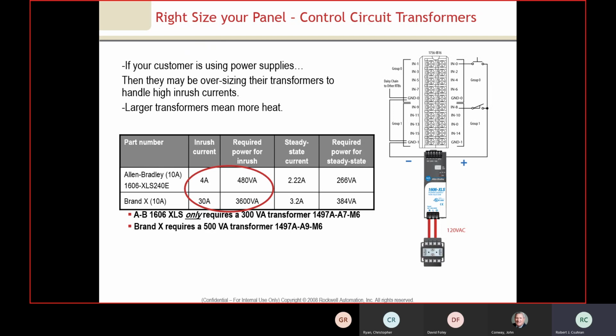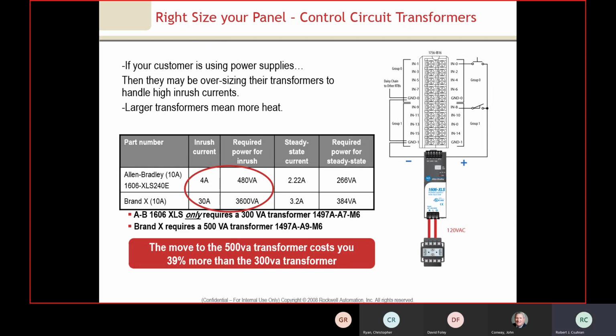The other thing that happens is if your incoming power needs to be stepped down, you also need to increase the size of the transformer. So you need to oversize the transformer to handle the higher inrush. The larger transformer means more cost, more panel space, and more heat. So you look at the bottom here, and utilizing the high efficiency power supply, we're able to use a 300 volt amp transformer versus a 500 volt amp with the other power supply used. So this does have a cascading effect when it comes to the cost, the heat, and the size on the power supply that's used. So in this case, we talk about the fact that it's almost 40% more cost for the larger transformer.